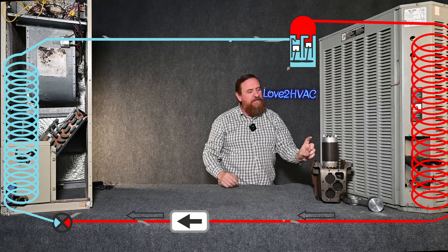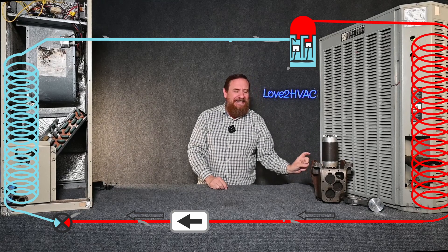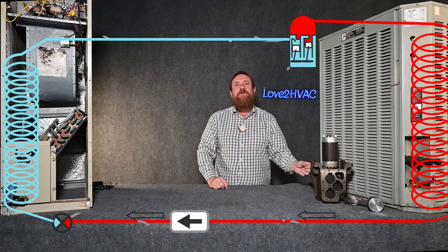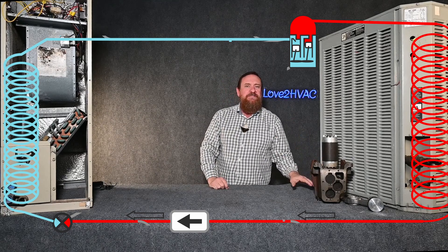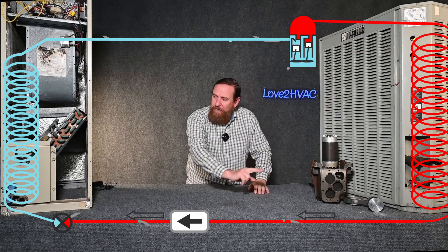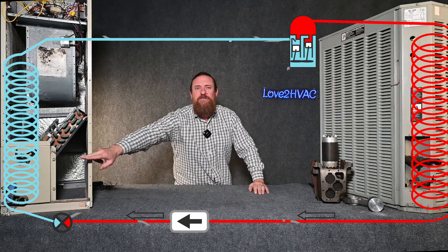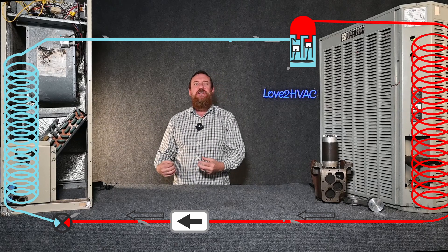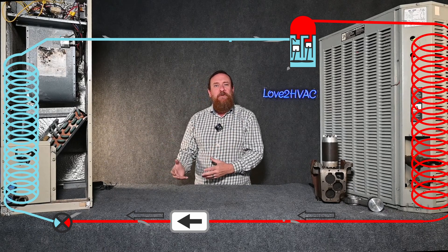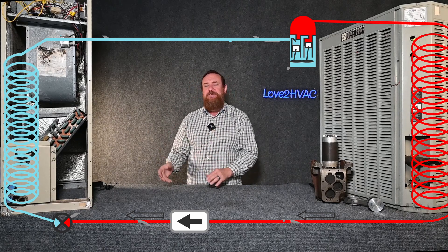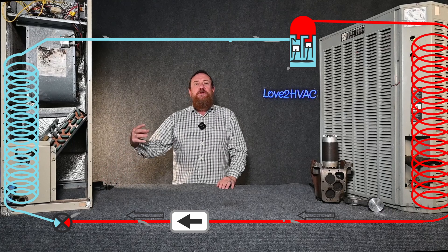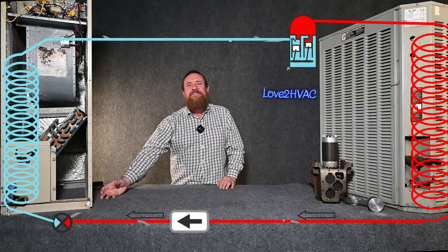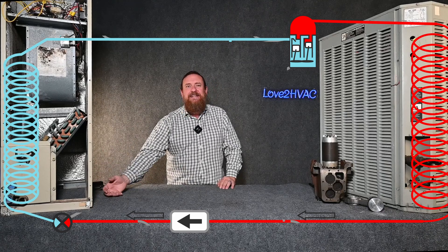Latent heat is taking place. Then we're going to sub-cool it — that last little bit of the condensing coil, we sub-cool that liquid below saturation. We send that sub-cooled liquid into our metering device. Our metering device drops the pressure, and by dropping the pressure, we drop the boiling point, dropping the temperature of the refrigerant in the evaporator. The refrigerant is now boiling inside the evaporator, absorbing heat.